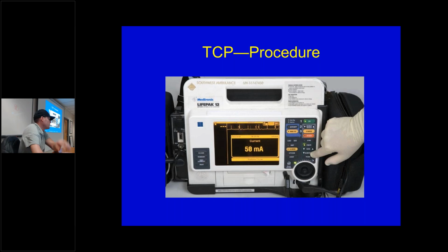You want to do the current at the threshold. And that was one of those key terms at the very beginning. But what do you think the threshold is? Threshold is the minimum amount of current required for capture. Okay? So you're increasing the current, and you don't want to necessarily do that super slow in a patient that's unstable, right? So you're kind of cruising up with the current, and as soon as you start to see capture, feel a pulse, then you can even hit it down a couple of times until it goes away, and then bump it up 2. So you want it 2 milliamps above the threshold. All right, the minimum amount of current to have capture.